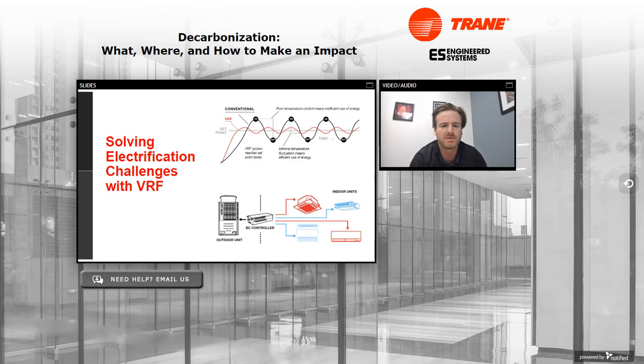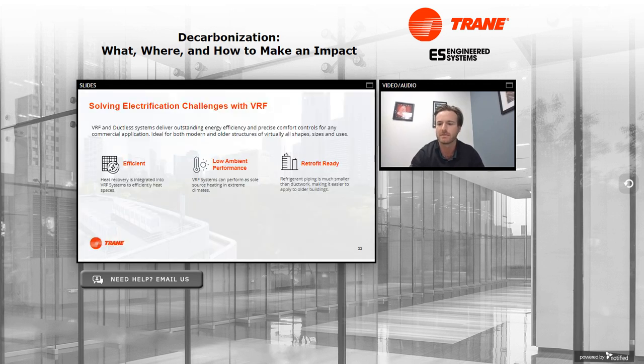The middle piece you see there, the BC controller, is another critical component of VRF systems. That's your branch controller, which allows for heat recovery within the space, simultaneous heating and cooling. This is critical because it essentially allows you to reuse heat within the space to cool other spaces, lowering your total load and improving the efficiency of the building.